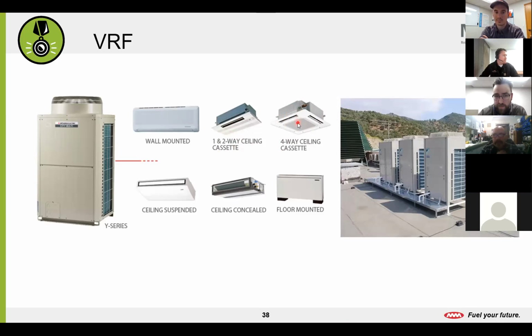Okay. So we have our ceiling cassettes here. These are going to be exposed units. They're mounted directly into the ceiling. The difference between the 1 and 2 way and then the 4 way is really just the number of directions we're able to throw that air. So 1 and 2 obviously can throw it 2 directions. A 4 way can throw it in all 4 directions to supply the space. Ceiling suspended system here is going to be very similar to a 4 way ceiling cassette or a 1 and 2 way ceiling cassette.